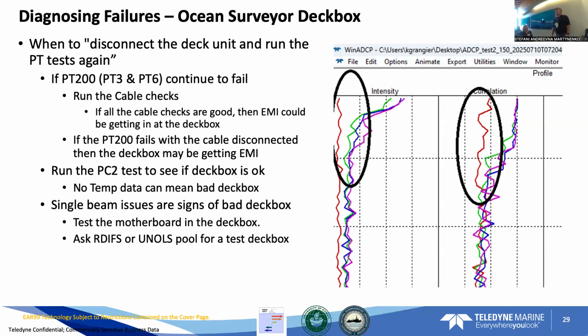And that leads to this one. So, when to disconnect the deck unit and run the PT tests. We run the PT 200 test, we'll run all of them, and if you're getting failures when the whole system's connected, we want to disconnect the deck box from it, because if all your cable resistance checks look good, then most likely the deck box is suspect. So we want to run the PT tests on the deck box. If the PT test fails, you probably got a bad deck box.